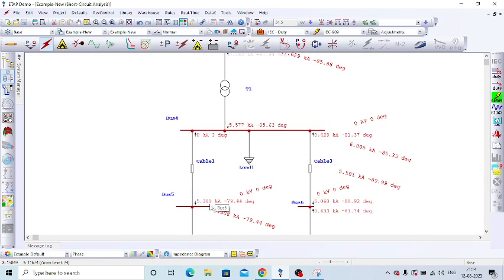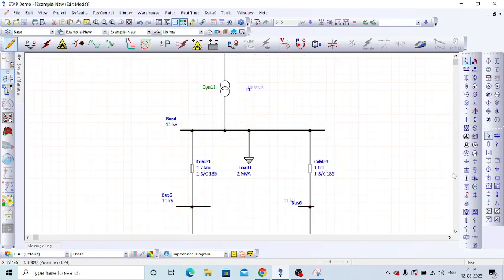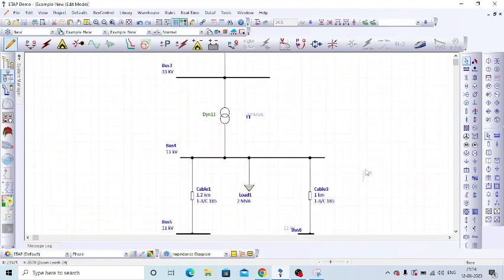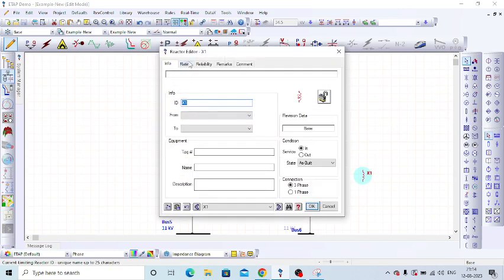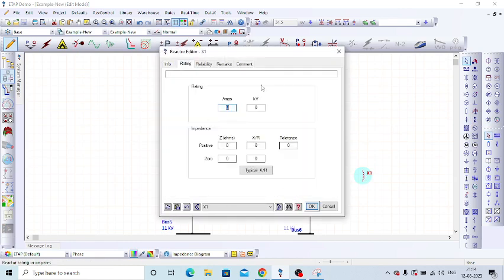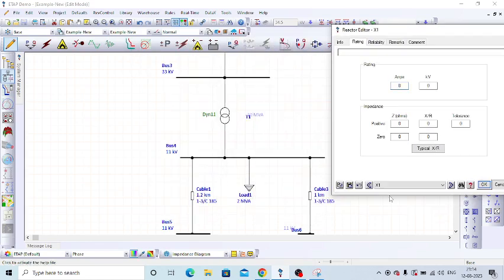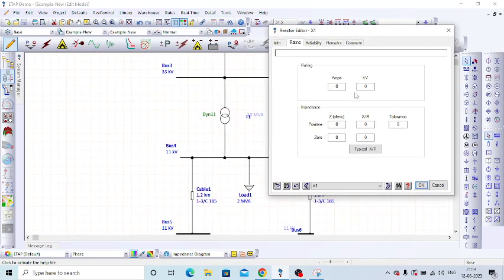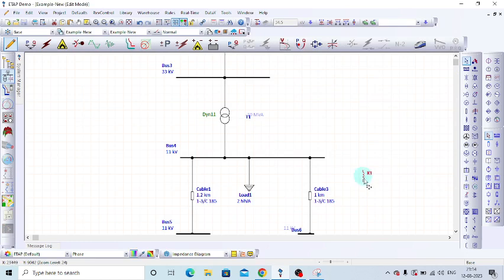So for that, what we can do is use a reactor, the fault current limiting reactor. Normally we add this reactor as a series reactor to the bus, so we connect it in between the bus. We have to select how much current we are limiting through this reactor, and then the reactor will limit the fault current. So this is called a fault limiting reactor. This is also one of the methodologies to reduce the fault current.